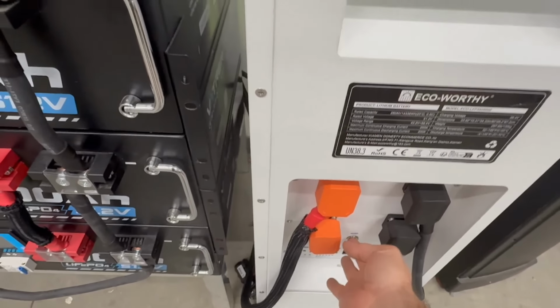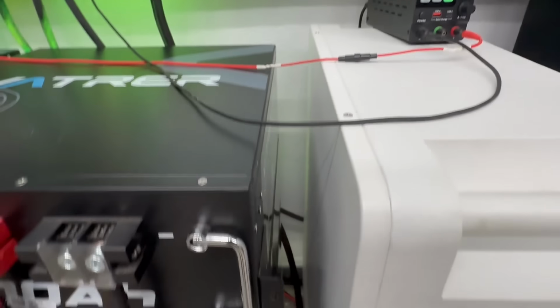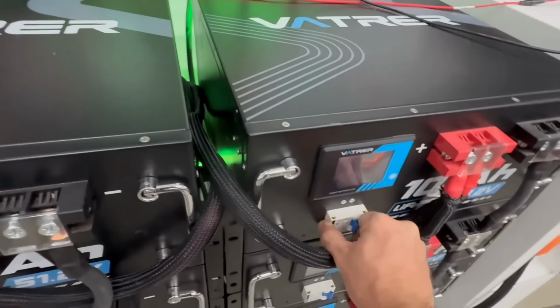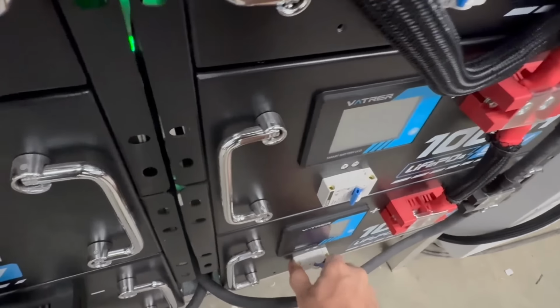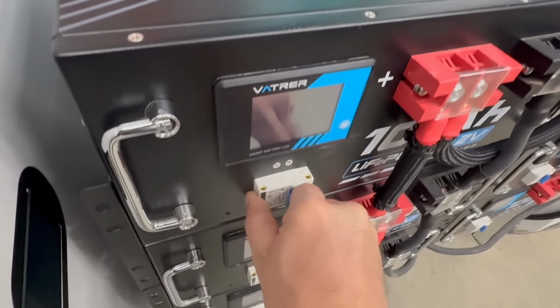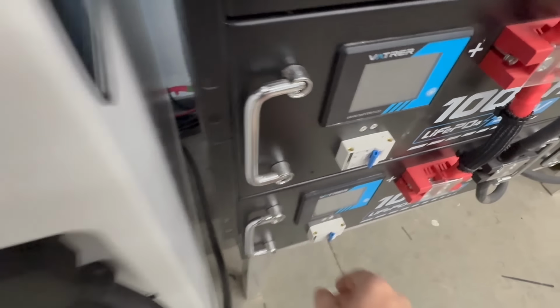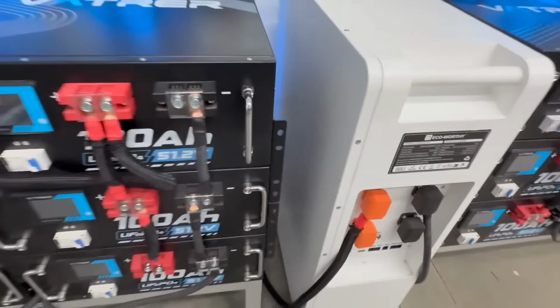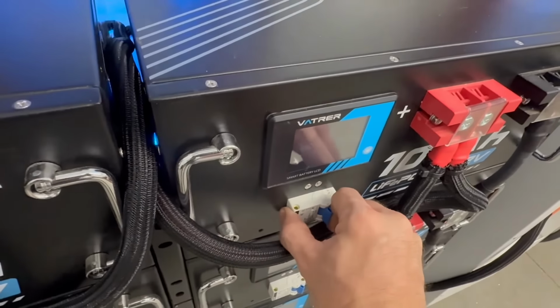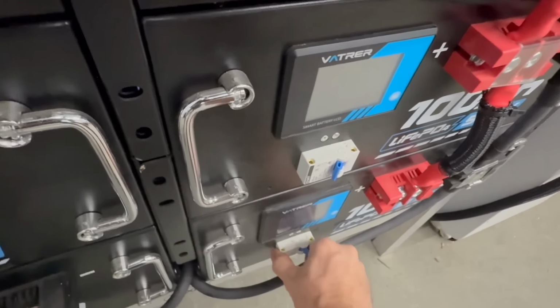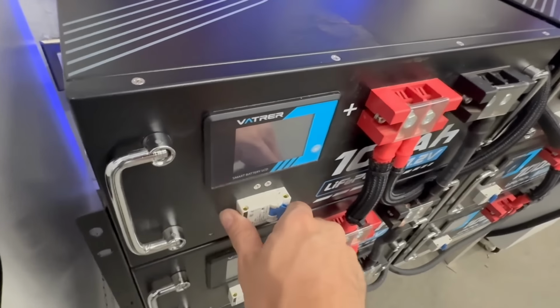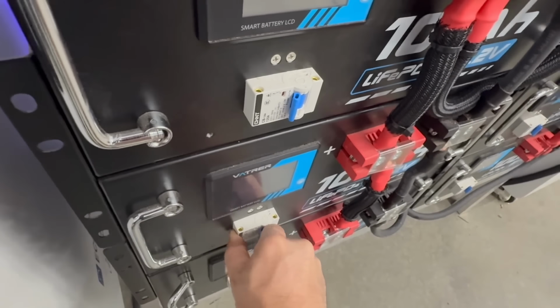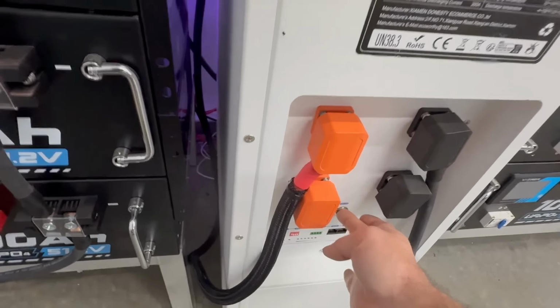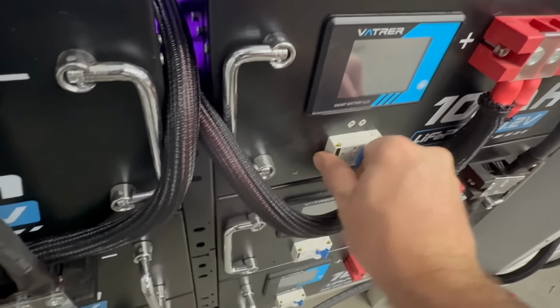All right, so now we'll flip on all these batteries. We're at 55 there. I'll power all these on. Remember, right now it's being powered by that power supply. As these batteries turn on, each one is going to send power, but there's not going to be an inrush because the inverters were already at 55 volts. So turning it on this way does not hurt a thing.